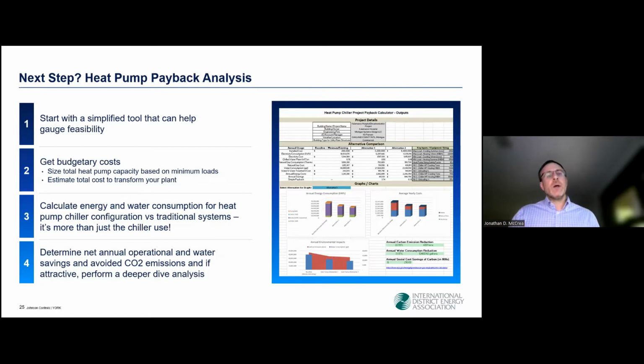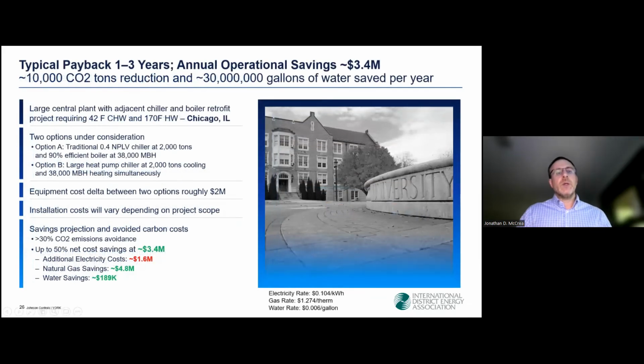All right, so next I'd like to share with you an example here. If we use this analysis tool, and this is just to give you a better idea of the magnitude of the savings that are possible here. So it's a hypothetical example, a large college campus with a base heating load in the summer of 19,000 MBH and a base cooling load in the winter of 1,000 tons.